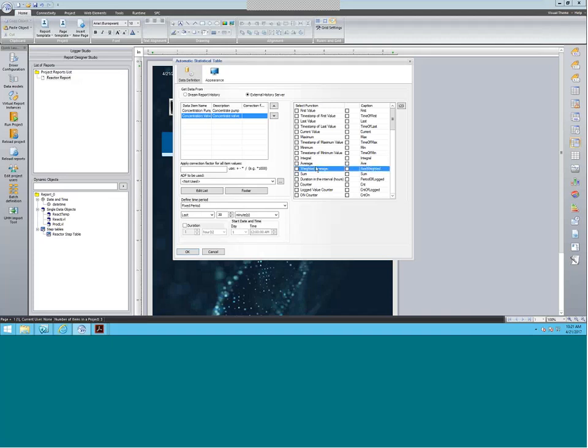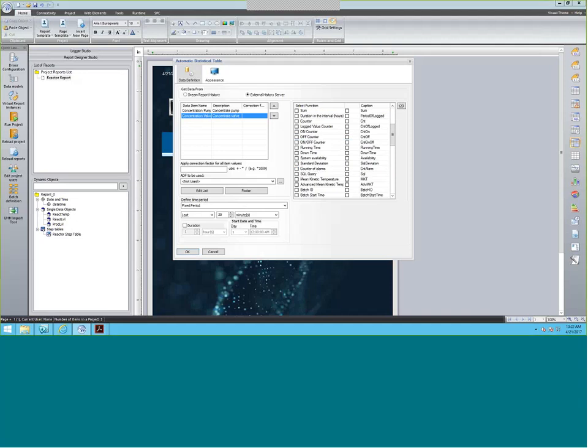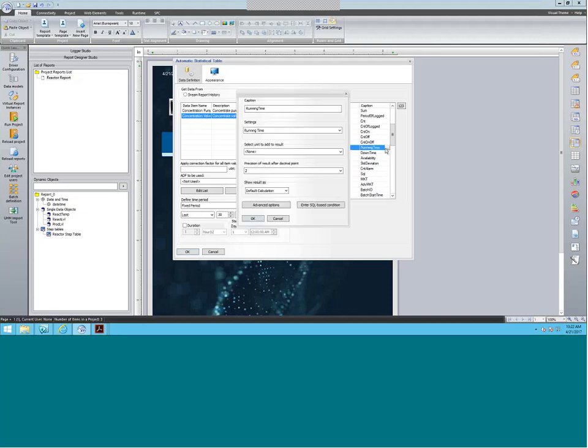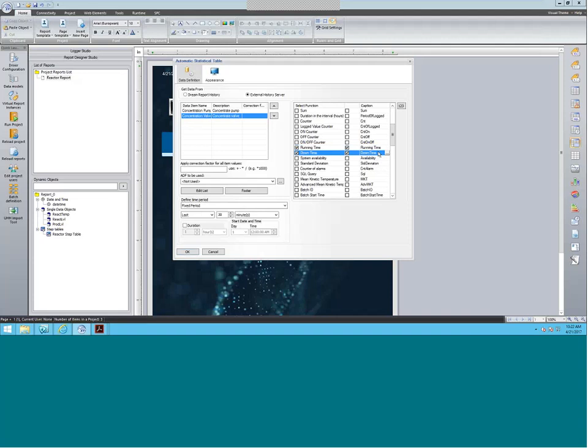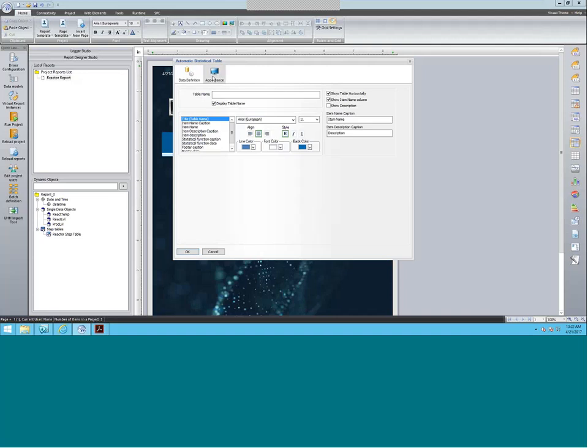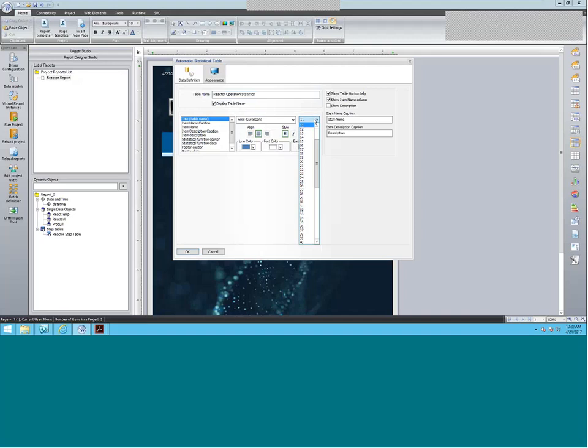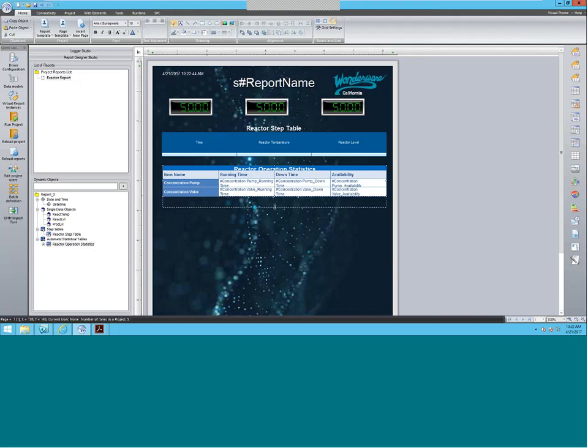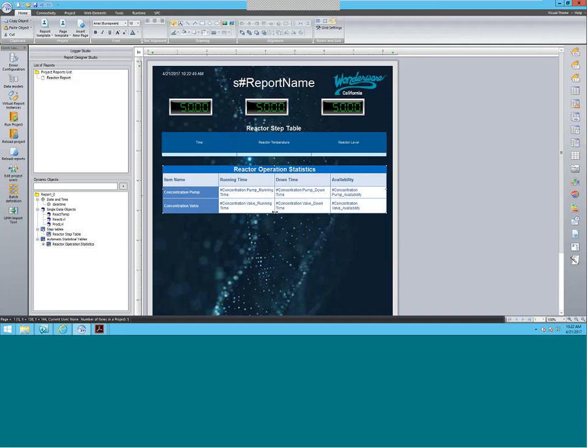Change the name here to concentration pump and concentration valve. Then selecting the points I want, I'm going to select the running time, the downtime. You can also change the display caption here — just put a space in there so it looks nice — as well as the system availability, how often that was available for the last 30 minutes. Then put in the name: we're going to say Reactor Operation Statistics. Name size, change it to 15 to make it look nice. You can also adjust the table sizes here if it looks weird.